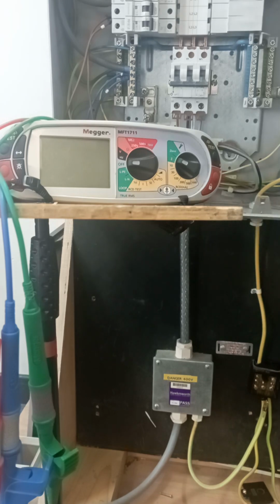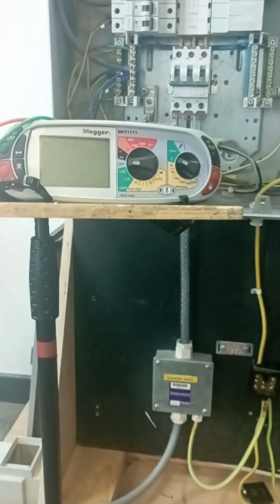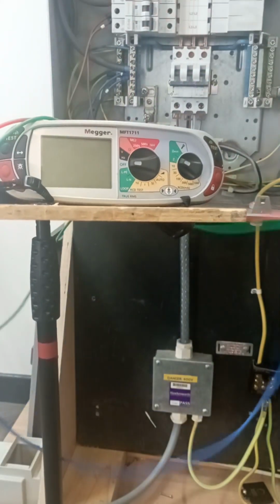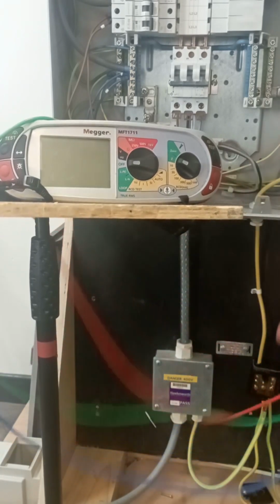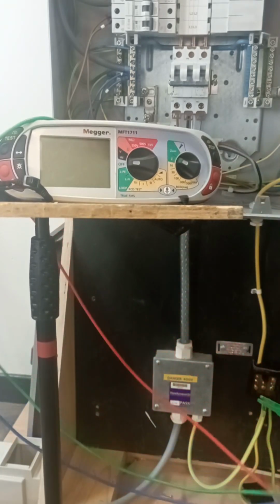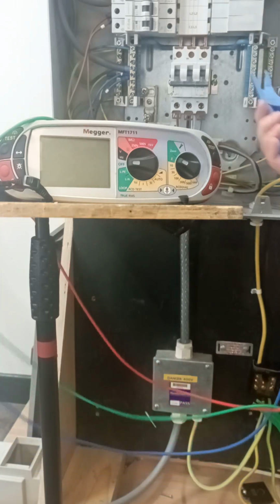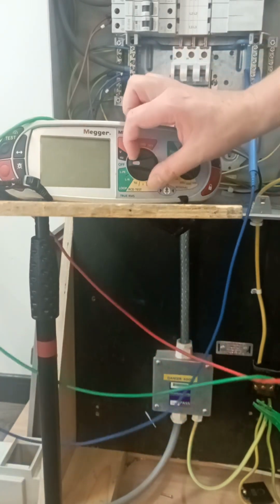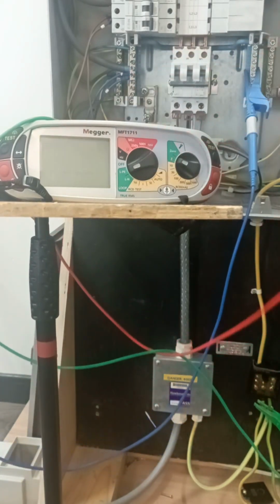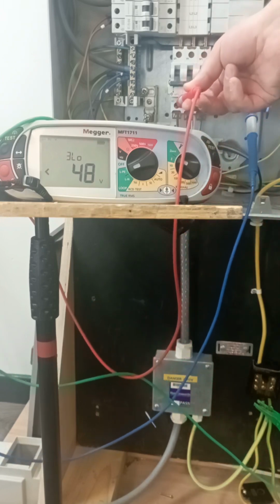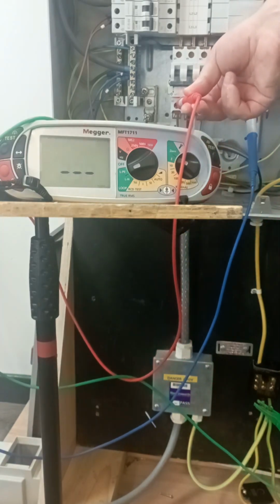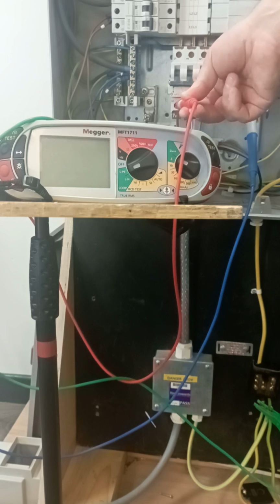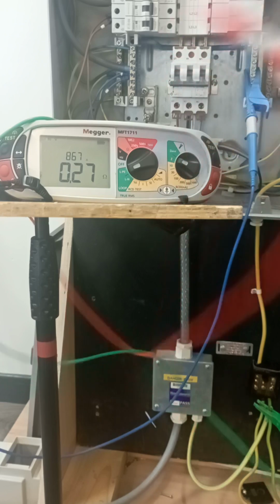wand. Okay, so now what I'm going to do is clamp my leads onto the meter, from the meter onto the disconnected earthing conductor. Make sure I get a good solid grip. I'm going to clamp onto the neutral terminal, and then set my meter to LPE and it's on Z. At this point I'm going to take my probe and stick it into the line 1 connection. You'll see this meter auto tests, so it told us we had 239 volts there. And we're looking for the ohmic value that we get on the screen. So you'll see there we have 0.27 of an ohm.